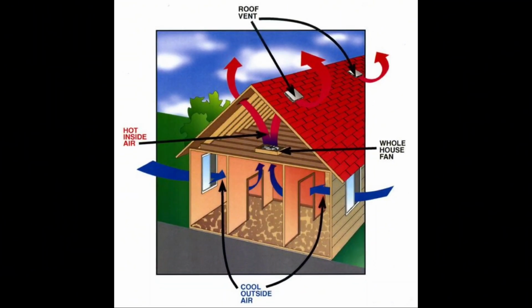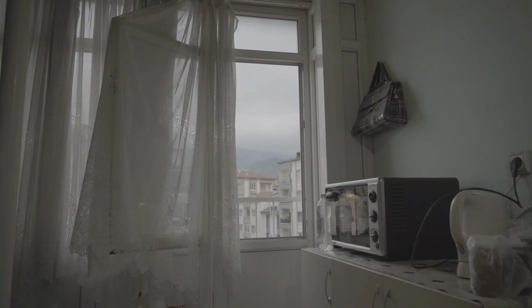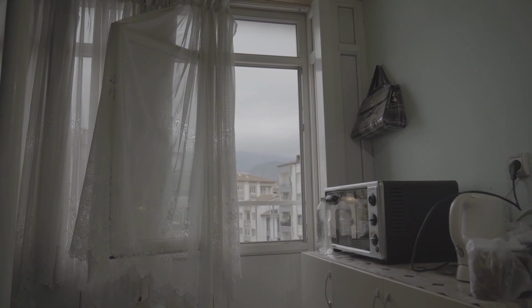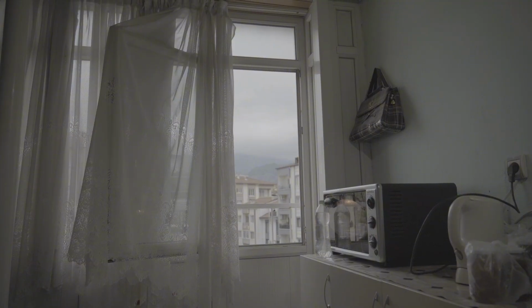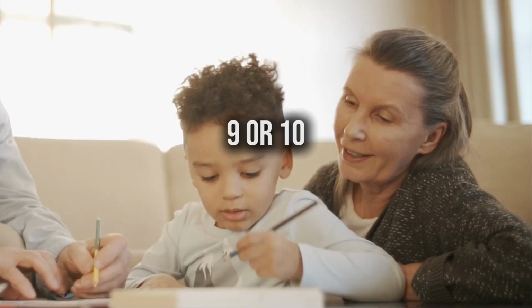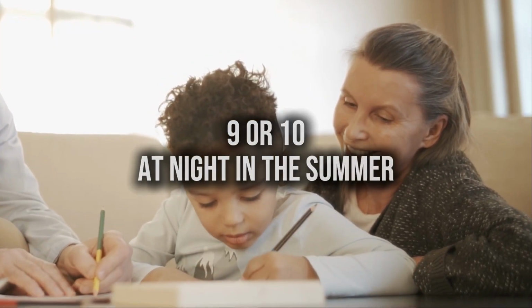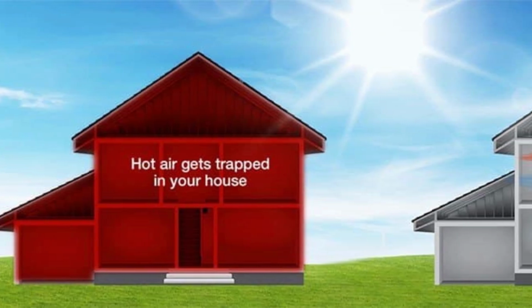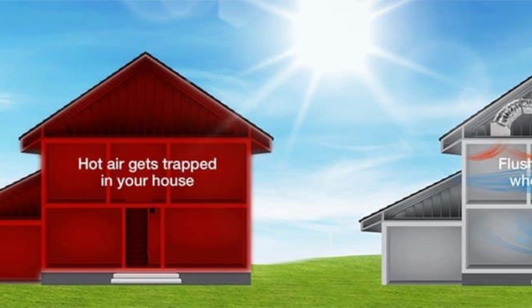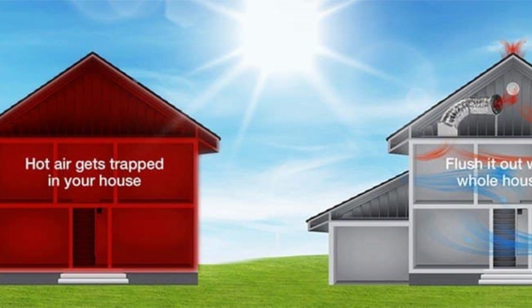The system worked best when the outside temperature dropped below the inside temperature. In most of the American interior, that crossover happens around 9 or 10 at night in summer. Run the fan for 2 to 3 hours after sunset, and the house would shed nearly all of the heat it had absorbed during the day.